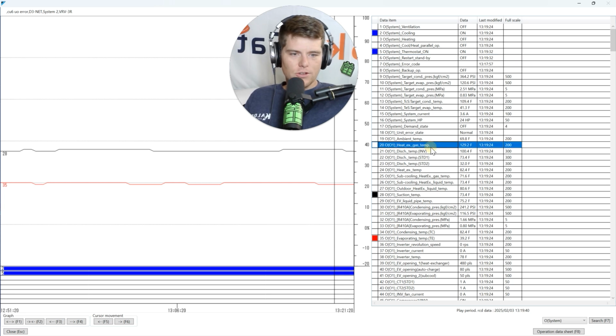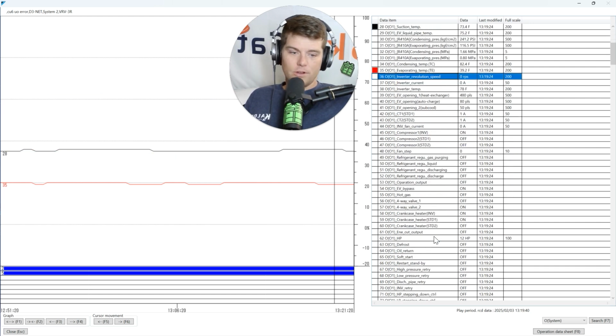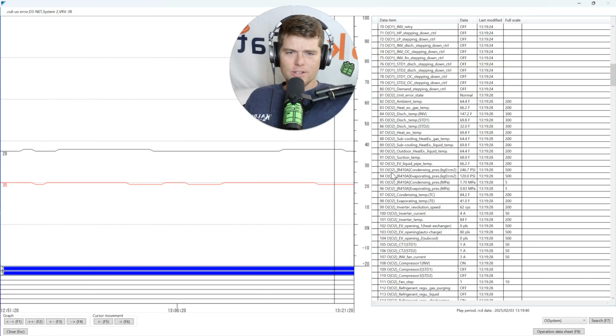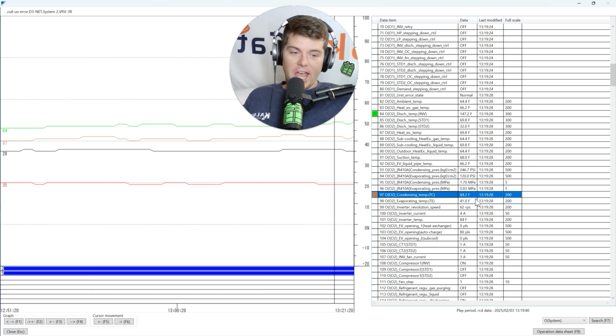Well, maybe about discharge superheat. Okay, heat exchanger gas temp. I could do inverter temp, but it looks like the compressor doesn't even run in this module. Well, let's go to the other module. REMQ series, right? VRV3, there's always a pair. Okay, inverter discharge temperature. Let's look at, let's see here, TC. Okay, so 147 minus 84, so that's about 60 degrees discharge superheat. That's not terrible. Looks the same.